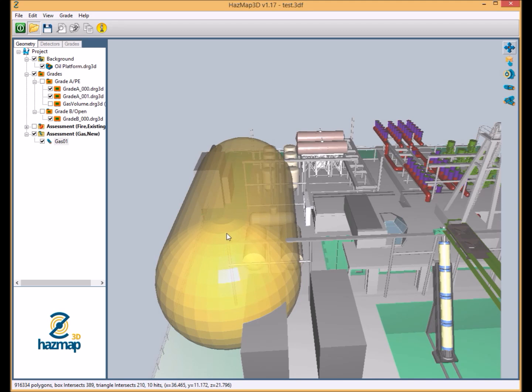It's important to note though that this is not 10 meter spacing. We're not simply being prescriptive. We would always encourage a performance-based design to try and justify what target gas cloud is being analysed.